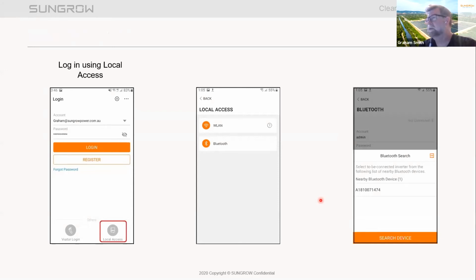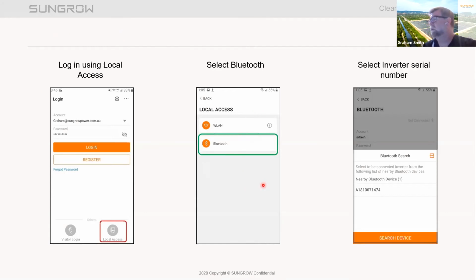So the first thing you do is open up the app, and instead of logging in, you see down here there's a little icon for local access. You're going to use this, and you're going to connect via the Bluetooth to the inverter. So you tap that little button here, and you'll get this screen here, and you select Bluetooth, and then it will scan for the inverters nearby through the Bluetooth.